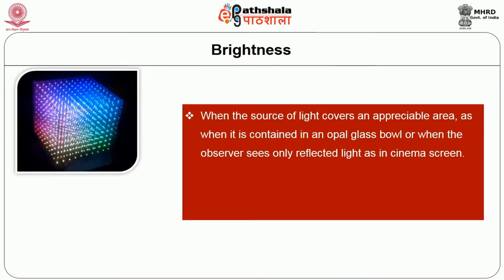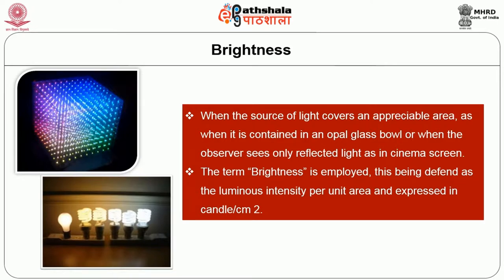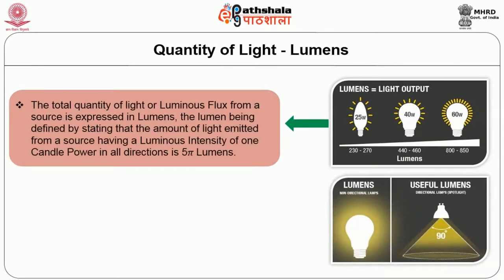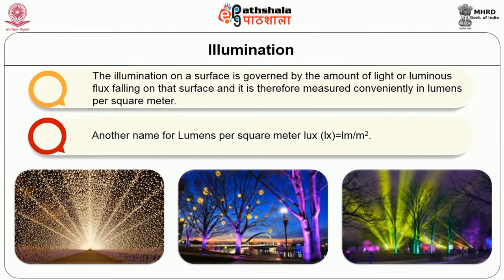Brightness: when the source of light covers an appreciable area, as when it is contained in an opal glass bowl, or when the observer sees only the reflected light as in a cinema screen, the term brightness is employed. This is defined as the luminous intensity per unit area and expressed in candle power per meter square. Quantity of light — lumen: the total quantity of light or luminous flux from a source is expressed in lumens. The lumen is defined such that the amount of light emitted from a source of one candle power in all directions is 4π lumens. An ordinary 60-watt lamp will have an output of about 700 lumens. Illumination on a surface is measured in lumens per square meter, another name for which is lux.